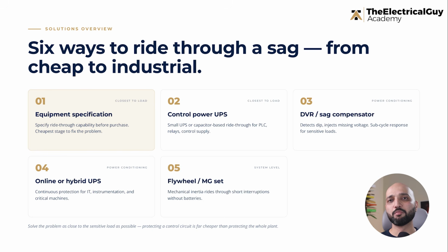The fifth solution is a motor generator set or flywheel system. A motor generator set uses mechanical inertia to ride through short interruptions. The motor drives a generator and the generator feeds the load. When input power dips or fails, the rotating inertia continues supplying power for a short time. Flywheel energy storage works on a similar basic idea, but with modern high-speed flywheels and power electronics, this system can provide ride-through for short interruptions without depending only on batteries. They are useful where frequent short disturbances occur and high reliability is required.